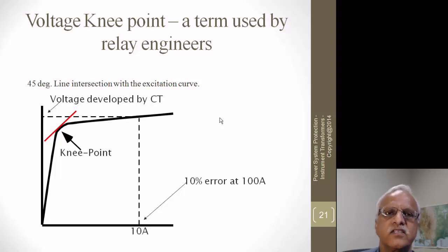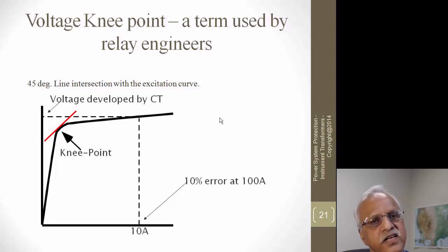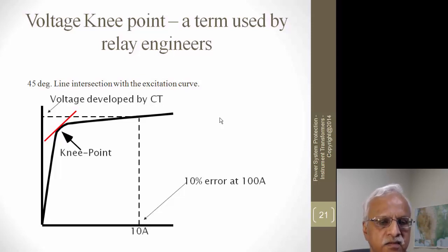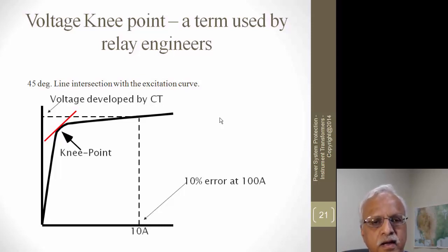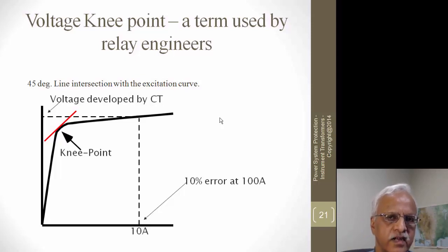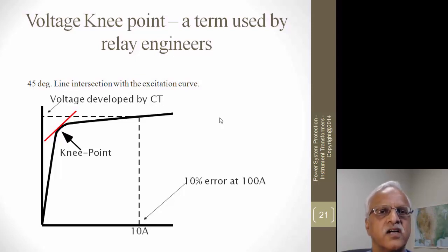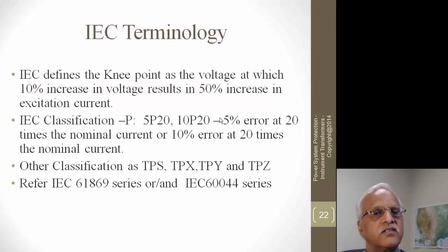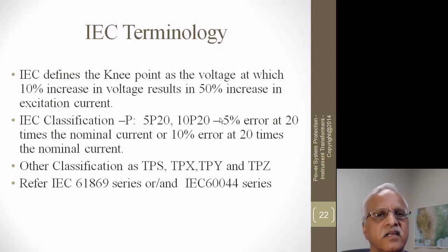There is another term used by relay engineers: the knee point. It indicates where the CT remains linear up to that point and starts saturating beyond it. ANSI defines it as the point on the excitation curve at a 45-degree tangent. As you apply increasing voltage to the secondary, it increases linearly up to that point, after which a small voltage increase causes a much larger excitation current increase. IEC defines the knee point as where a 10 percent increase in voltage results in a 50 percent increase in excitation current.